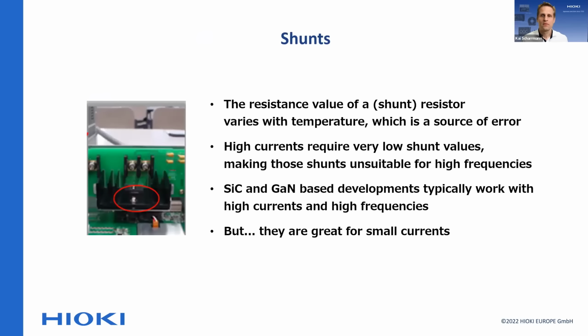And so if we summarize that, basically, shunt resistor values vary with the temperature. You can use a high current or a high frequency shunt, but typically not at the same time. And the tricky bit is, if you look at power applications nowadays, especially those with SiC and GaN, the frequencies are becoming higher and higher, and the currents are going up and up again. So that makes the usage of shunts for those applications pretty tricky.